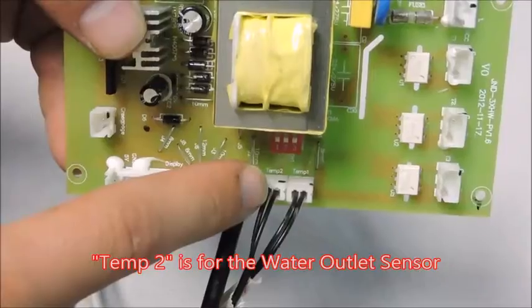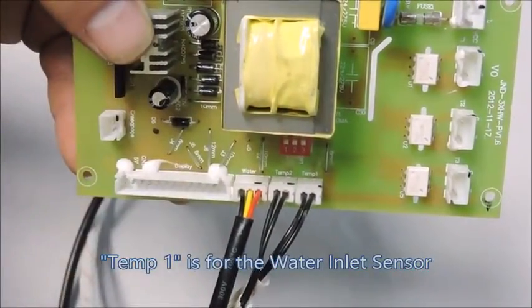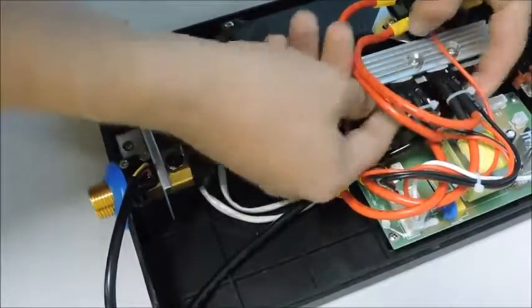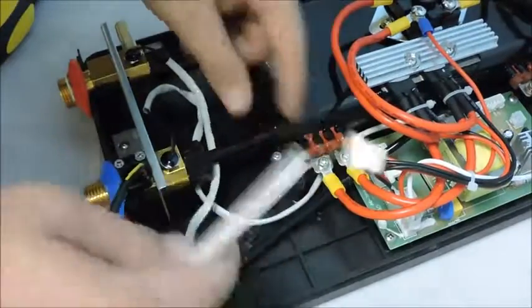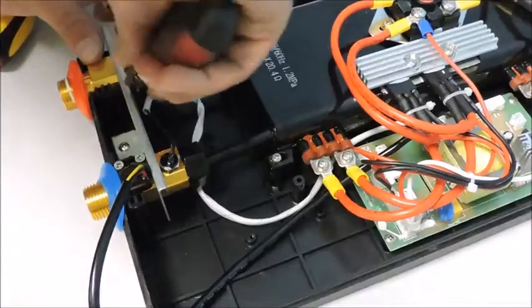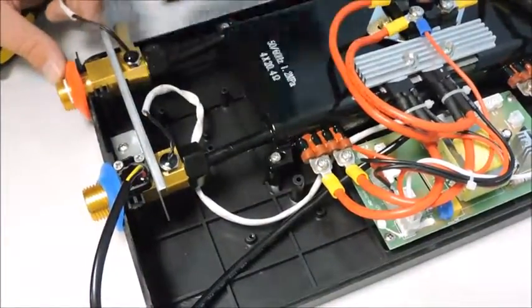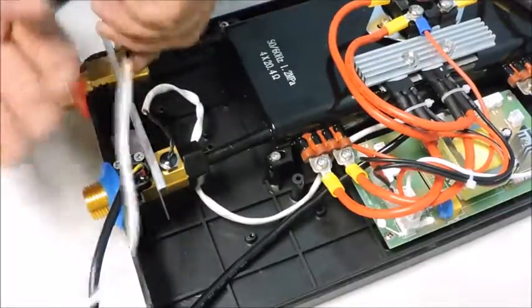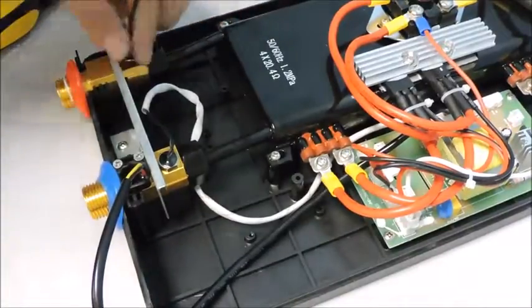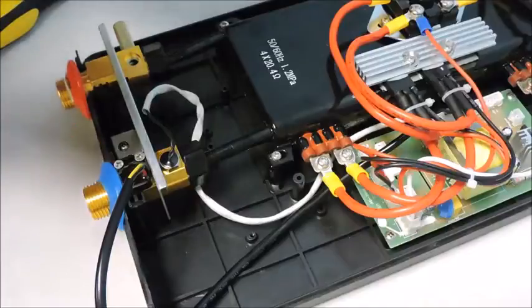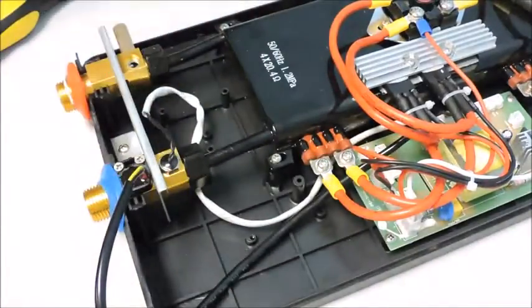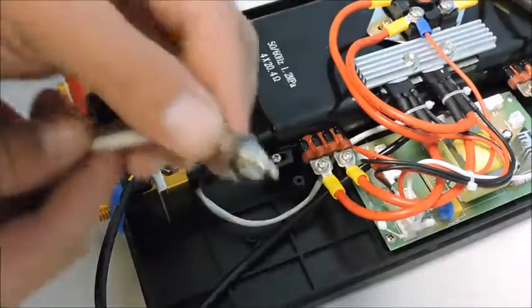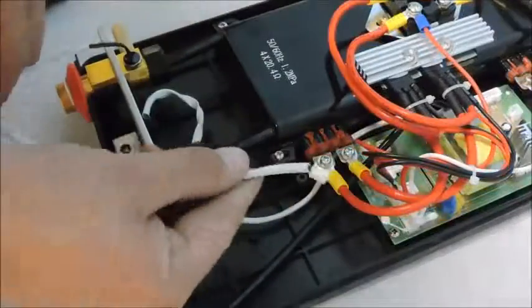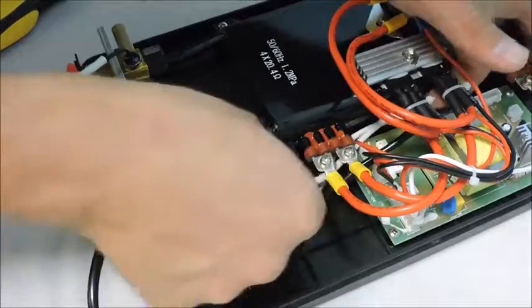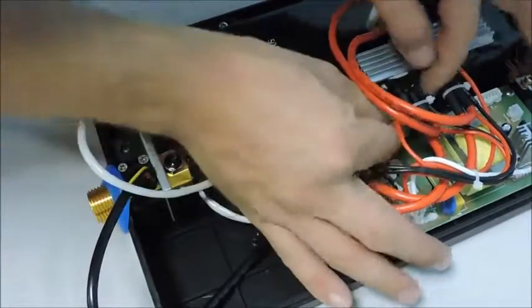Follow the hot water outlet sensor up to the connection point indicated on the board as Temp 2. Remove the wire and unscrew the faulty sensor. Screw in the new sensor and weave the wire back to the connection on the board, making sure to go under the power wires. Next, reinstall the wire retainer, making sure not to pinch any wires in the process.